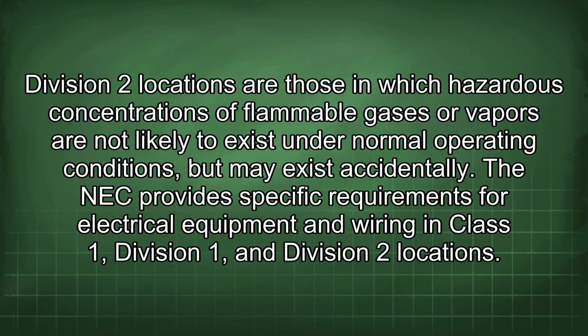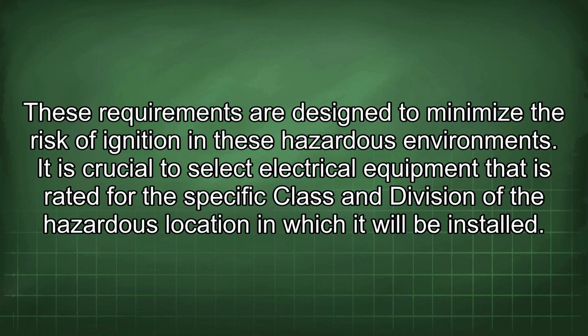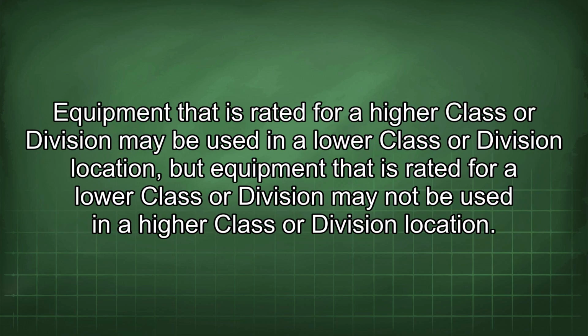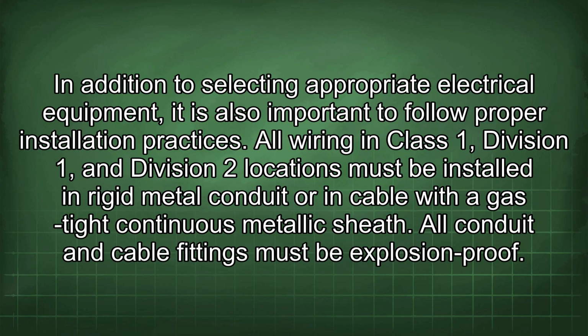The NEC provides specific requirements for electrical equipment and wiring in Class 1, Division 1, and Division 2 locations. These requirements are designed to minimize the risk of ignition in these hazardous environments. It is crucial to select electrical equipment that is rated for the specific class and division of the hazardous location in which it will be installed. Equipment that is rated for a higher class or division may be used in a lower class or division location, but equipment that is rated for a lower class or division may not be used in a higher class or division location.